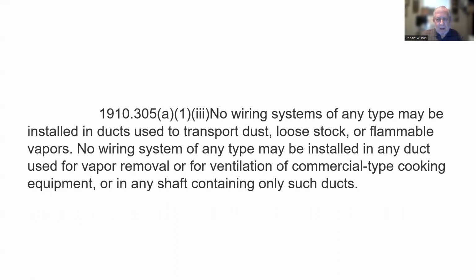No wiring systems of any type may be installed in ducts used to transport dust, loose stock, or flammable vapors. No wiring system of any type may be installed in any duct used for vapor removal or for ventilation of commercial type cooking equipment, or in any shaft containing only such ducts. And that makes a lot of sense. You really want to put an electrical conduit in a duct work, let's get the flammable vapors in there.